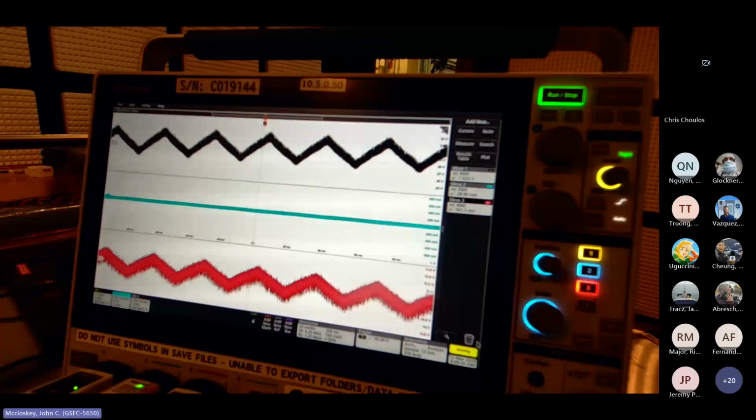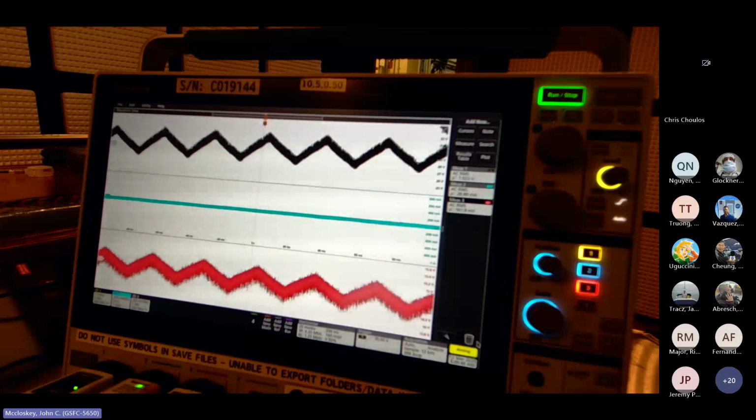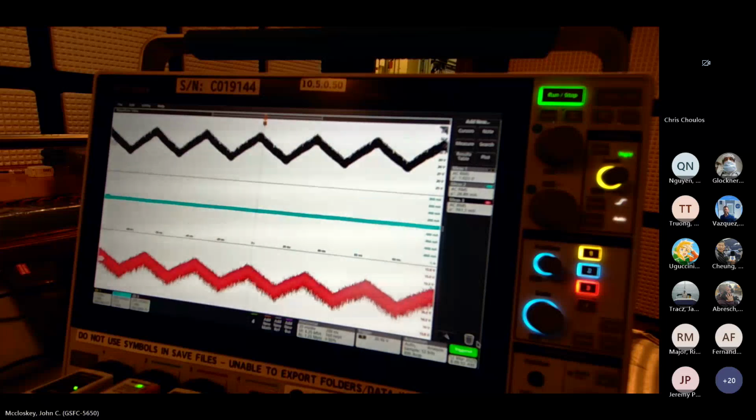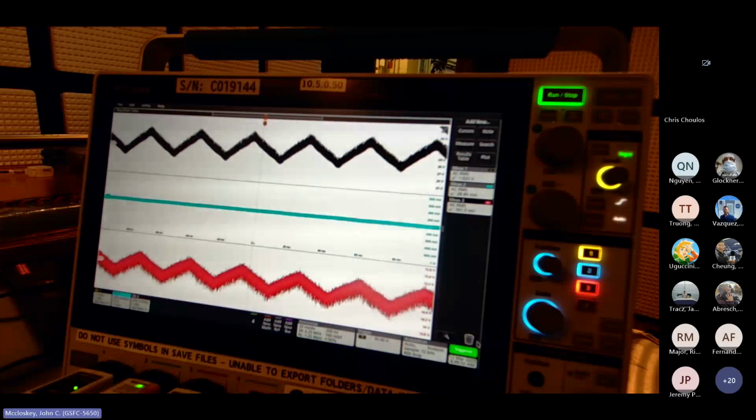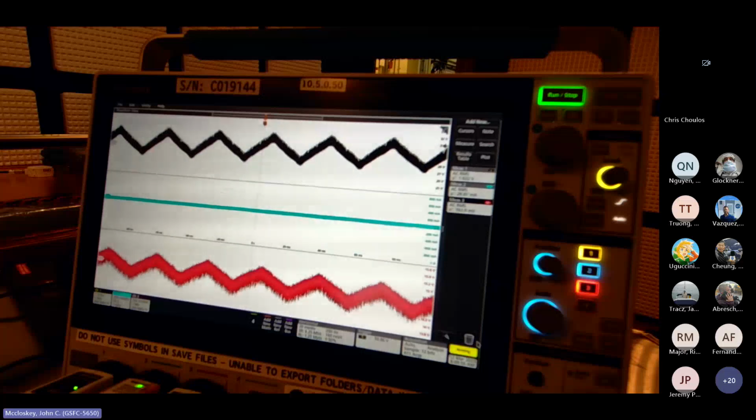Now, if you're doing the direct current monitoring method, you can just go straight to that, and that is a recommended approach that a lot of people take. You just hook up your current probe if it's part of your control loop. If you're just looking at it for information, then you still need to do the pre-calibration step.